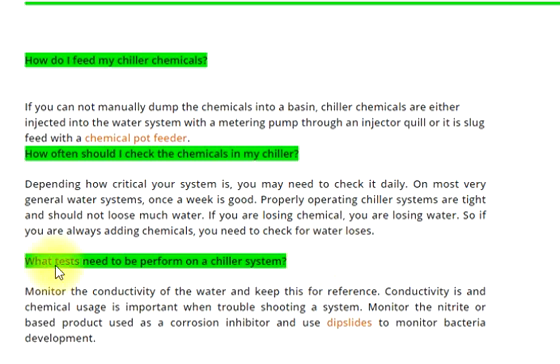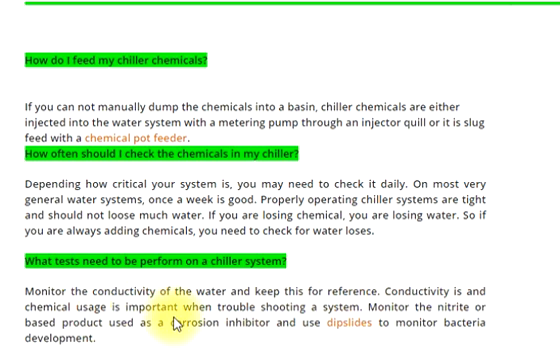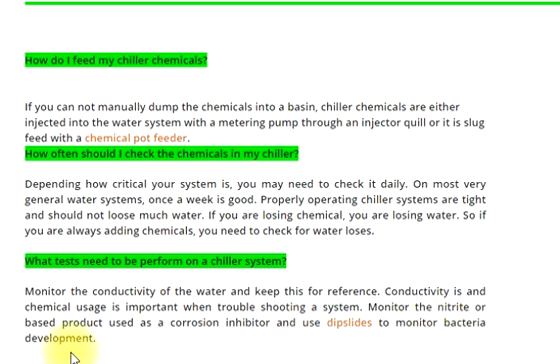What tests need to be performed on a chiller system? Monitor the conductivity of the water and keep this for reference. Conductivity and chemical usage data are important when troubleshooting a system. Monitor the nitrite-based product used as a corrosion inhibitor and use dip slides to monitor bacteria development.